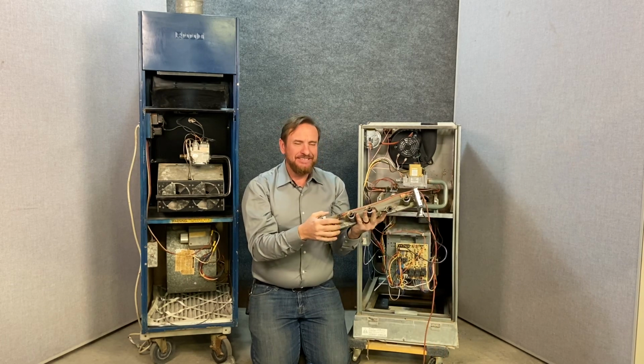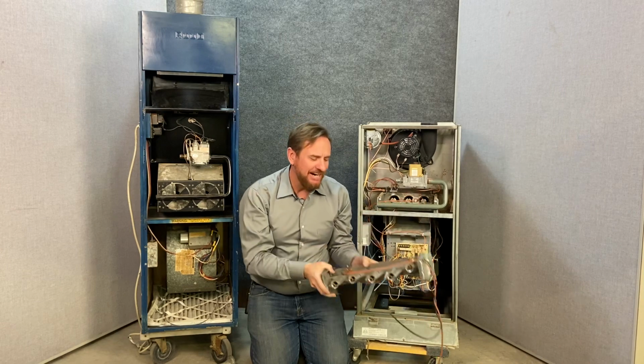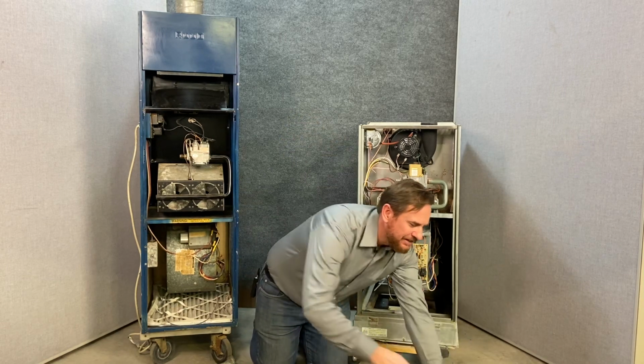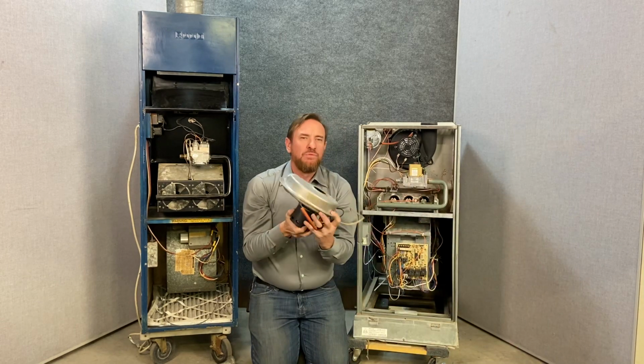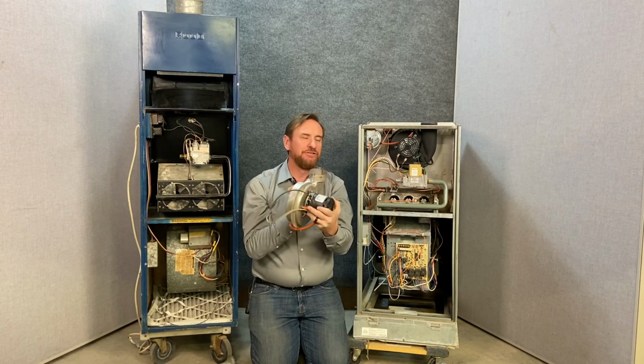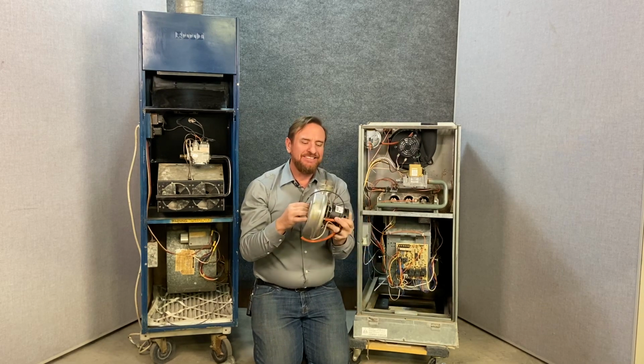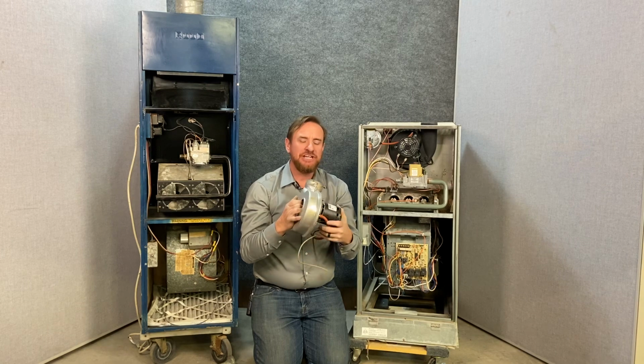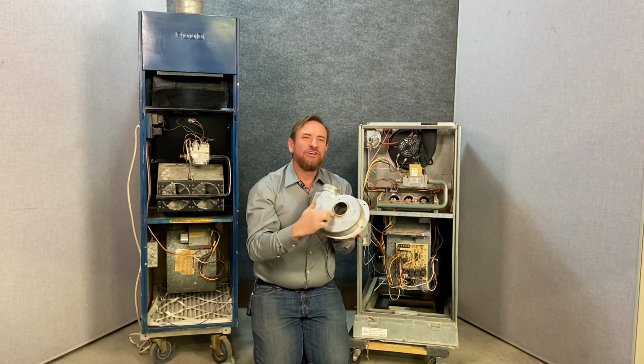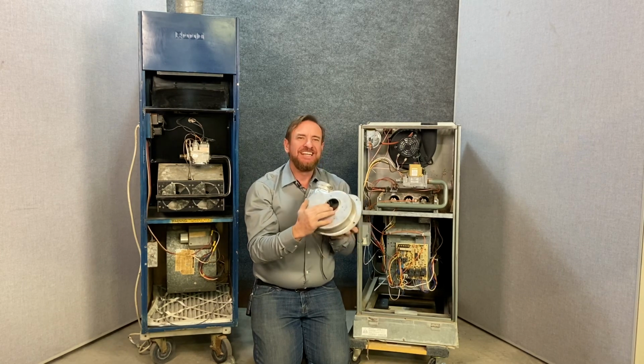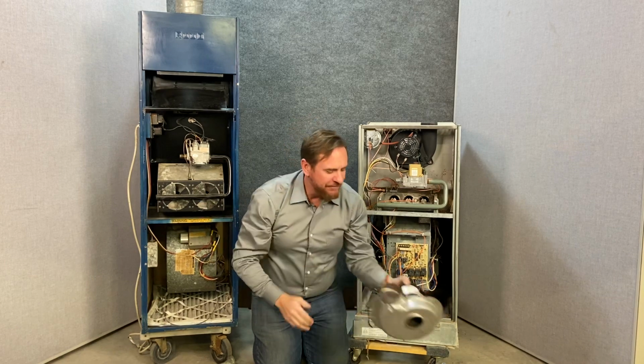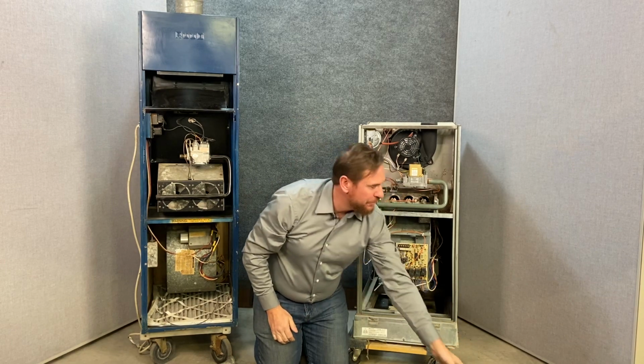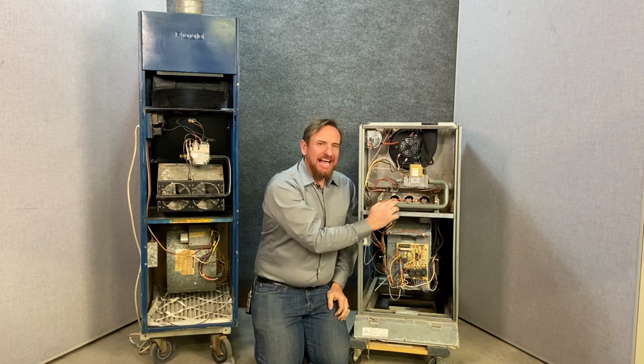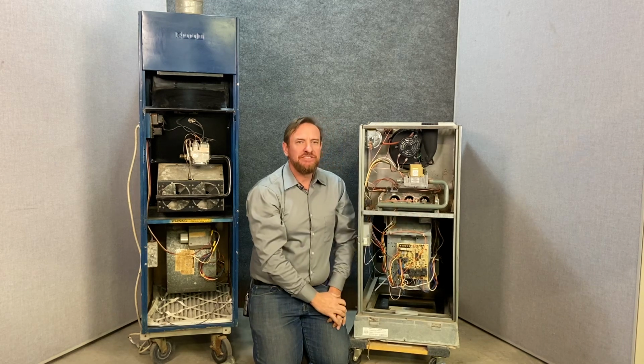This makes it nice and simple, but you think, how is it mixing the air and the fuel? And the engineers have done a significant amount of work for us. What they've done is they've put in this inducer motor that we talked about. They've designed this motor so they know exactly how much air it moves. And by having a precise hole right here, this will move an exact amount of air. Now, if we know exactly how much air is being moved, and they know exactly how much gas is in here, there's no need to adjust the air.